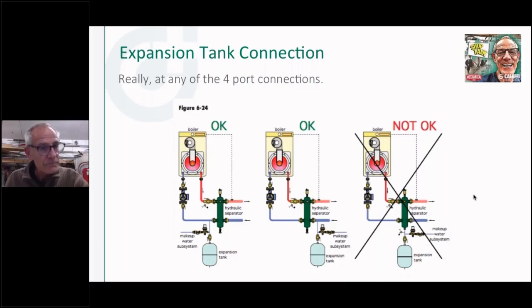Can you hear me? We can. Okay, good. I wasn't talking about pumping into the expansion tank, never was. When you pump on the boiler, the temperature's at the highest temperature, lowest pressure, best opportunity to get the air out of it. So that's counterintuitive to me, and what I've been doing for 40 plus years.